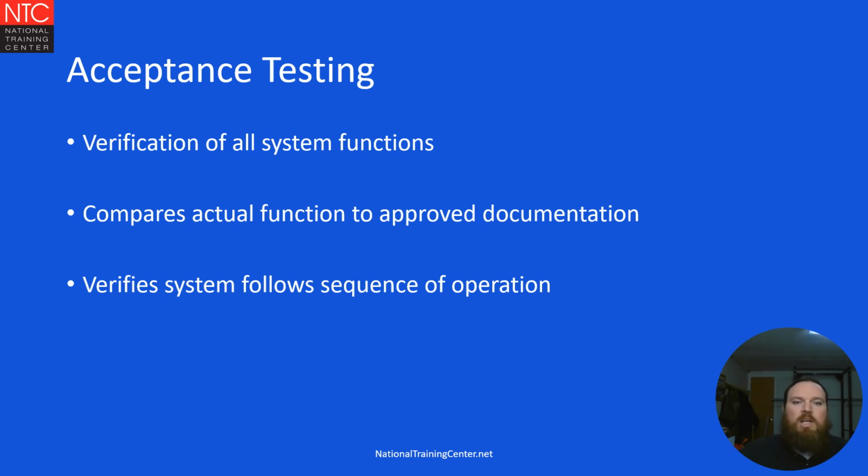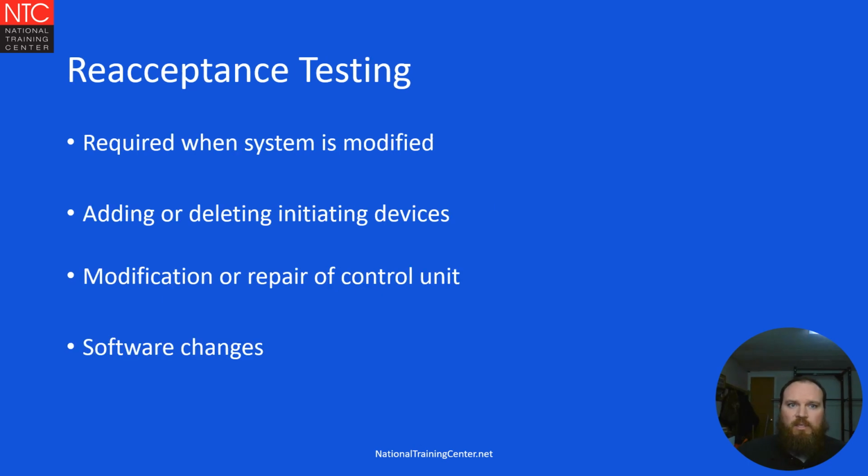We're going to compare the actual functionality of the system to the approved documentation that we have on this fire alarm system. And through all of these things, we're also going to be verifying that the system follows the sequence of operation. Whatever happens out in the field has to line up with that IO matrix.